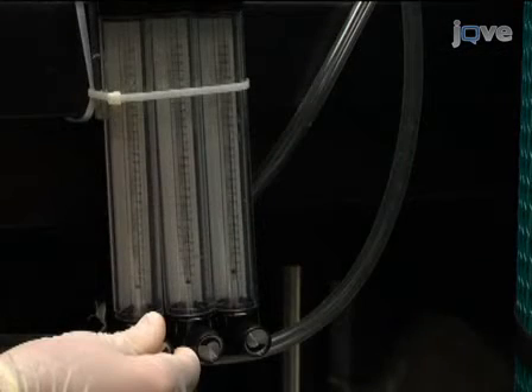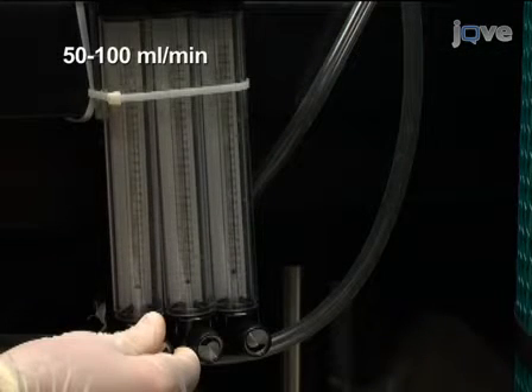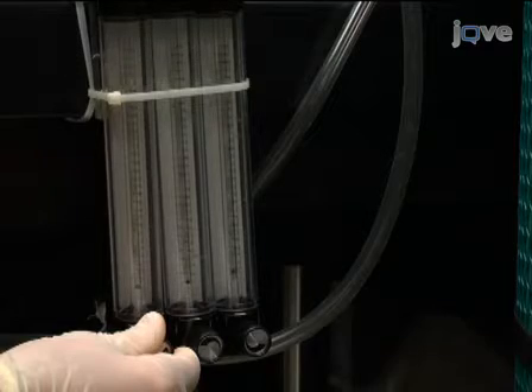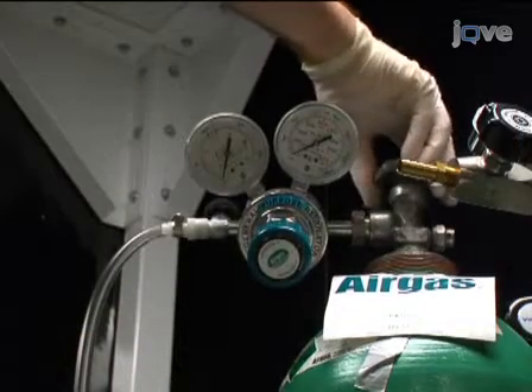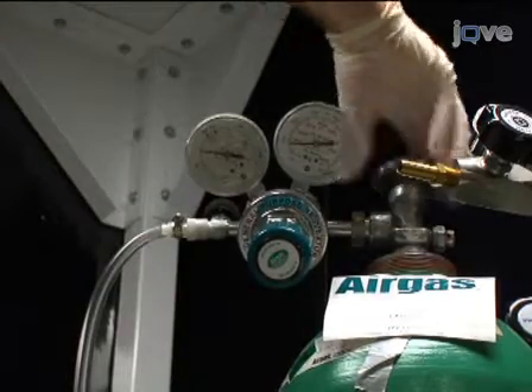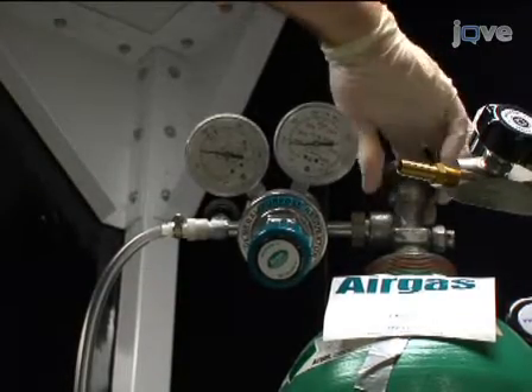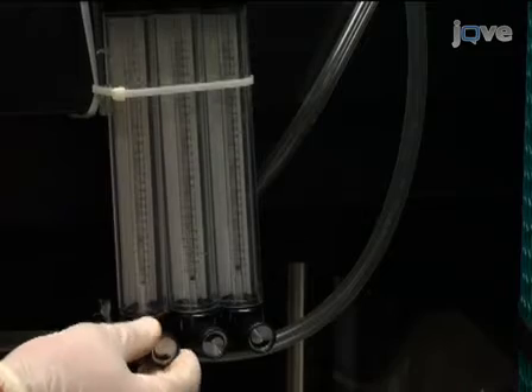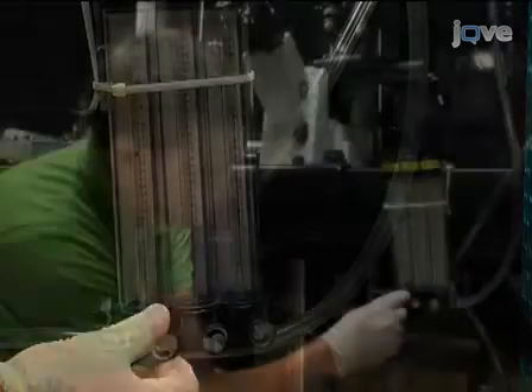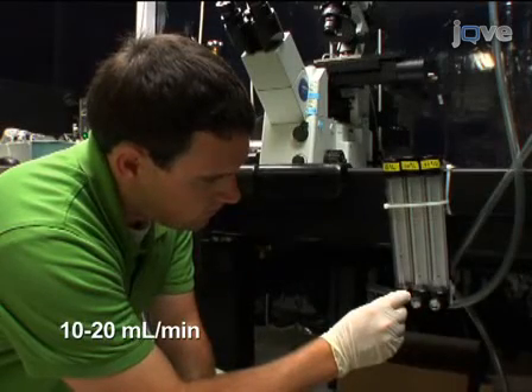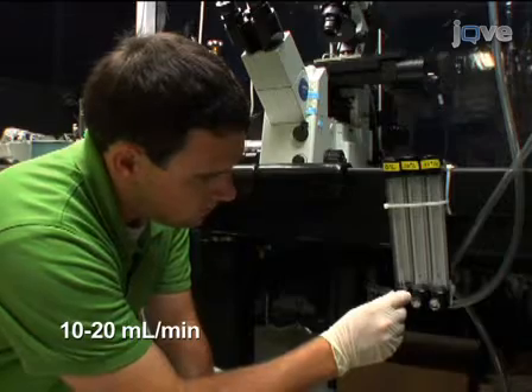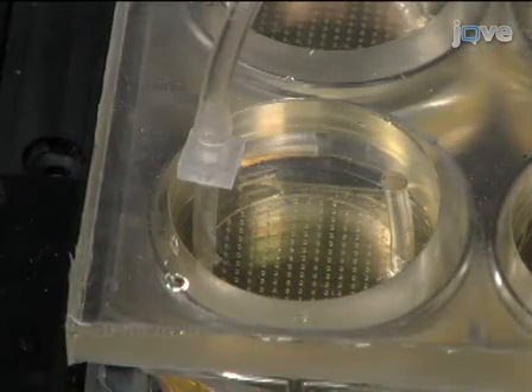A precision flow regulator, set to a flow rate of 50 to 100 milliliters per minute, is used for fine control of the delivered gas. Making sure the precision flow regulator is closed, open the tank top regulator first, followed by the precision regulator. Reduce the flow rate to between 10 to 20 milliliters per minute after 15 minutes to avoid creating bubbles in the water.